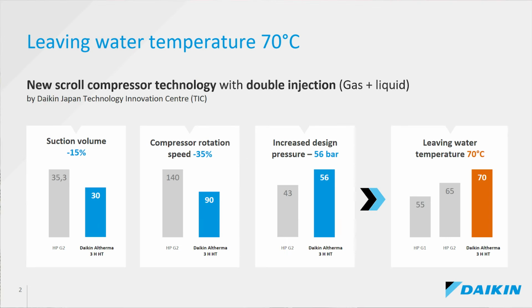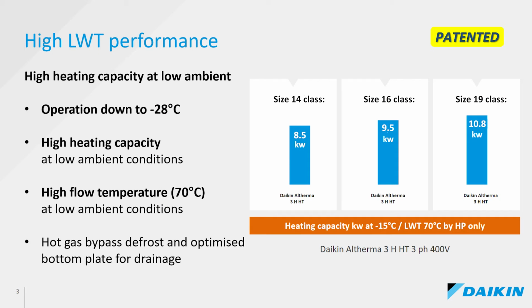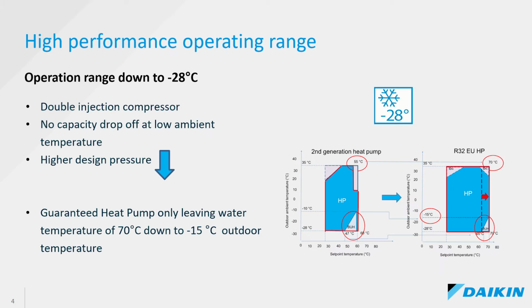The system provides a maximum leaving water temperature of 70 degrees in space heating mode and in operation range down to -28 degrees. It provides a guaranteed leaving water temperature of 70 degrees only from the heat pump down to -15 degrees outdoor temperature. Another great benefit of the Daikin Altherma 3 H HT integrated unit is that it's easy to install with all the components easily accessible.